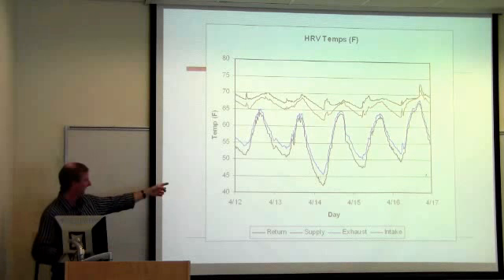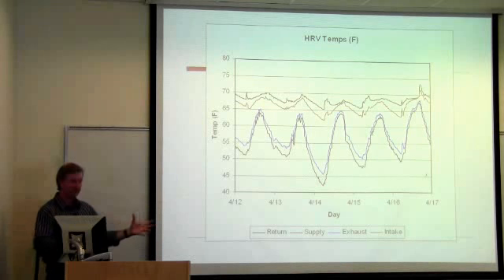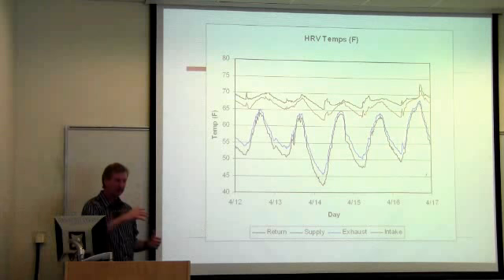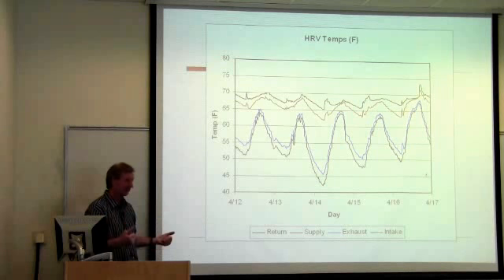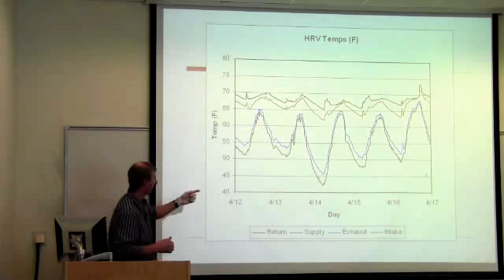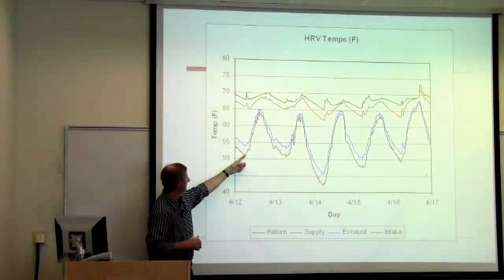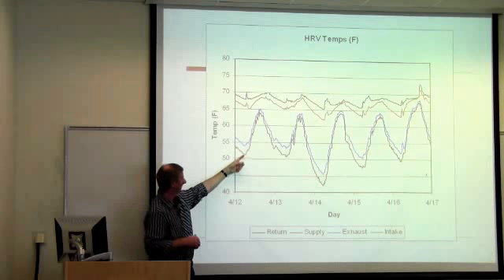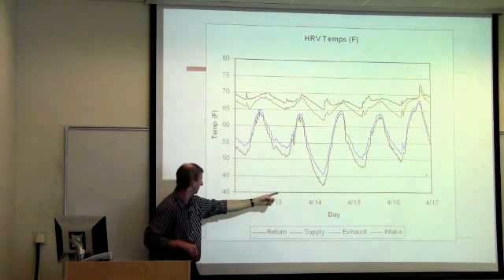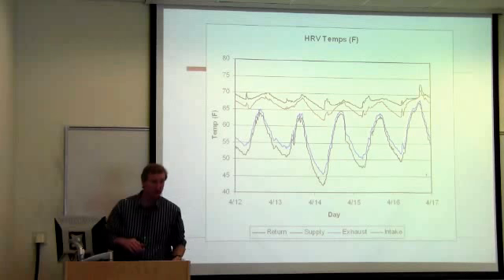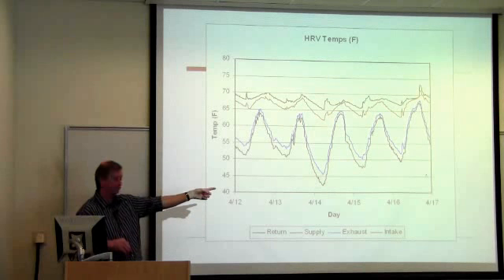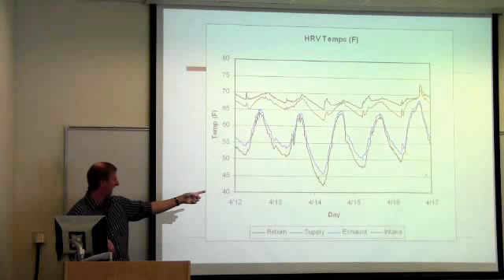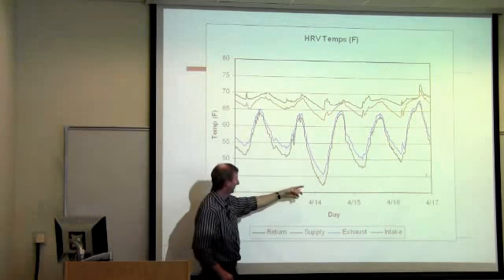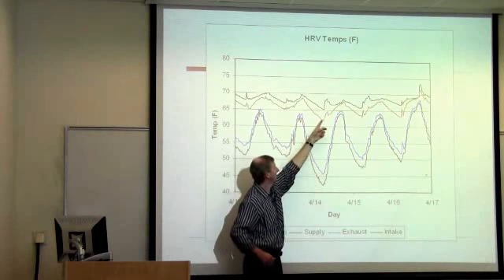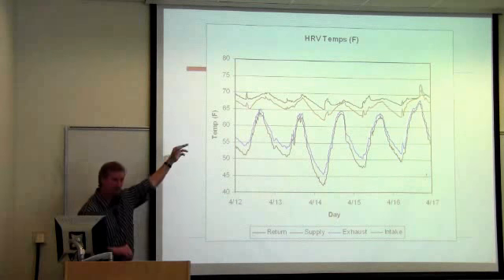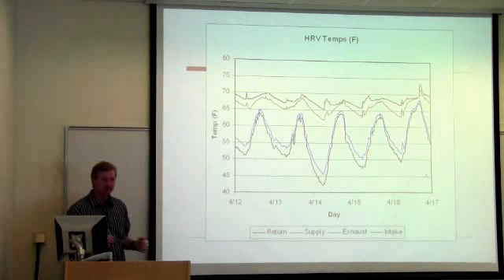So this house, beginning of April, they weren't heating it at all, so they're just using solar heat gains and heat gains throughout the house. So no active heating system. And it's just showing the HRV, the temperature coming into the HRV, say this is in the middle of the night, and then down here it comes in at 43, so kind of like the temperatures are now. Your temperature is around 43, so it's the same time of year at night. However, as it goes through the heat exchanger, it's warmed up to this temperature. And then the top line is showing the exhaust temperature coming from the bathroom.